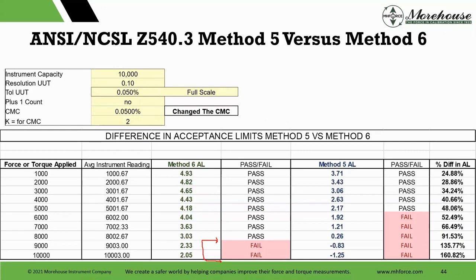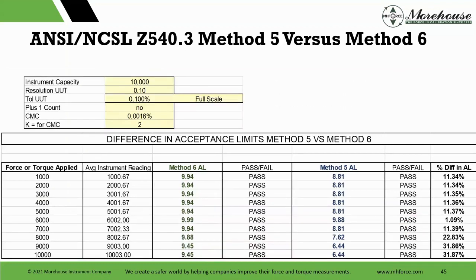So when we use the formula correctly, we see the true picture, right? And this true picture is, hey, with these measurements, if I made these same measurements and my measurement uncertainty was higher, I would not be able to pass the instrument. So that's with the tolerance of this. Then we're going to say, hey, right here, now we're going to raise the tolerance. So I used the lab that was 0.05. I want a conformity assessment. They're failing it, so what do I do? Well, maybe you need to change your tolerance. If everything's failing on the decision rules, this is a probability that you might need to change your tolerance. And manufacturers don't always get this, right? They sell an instrument, they say this, they say that, but do they all have metrologists that understand these decision rules?